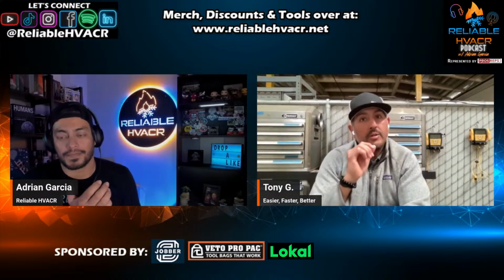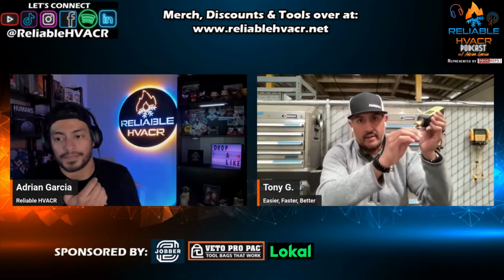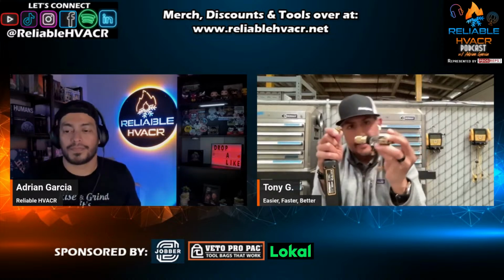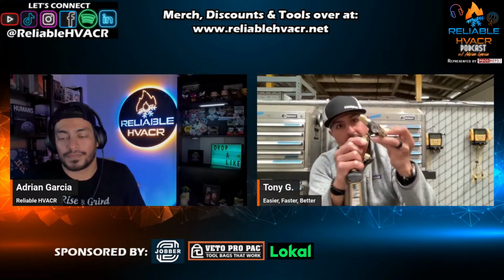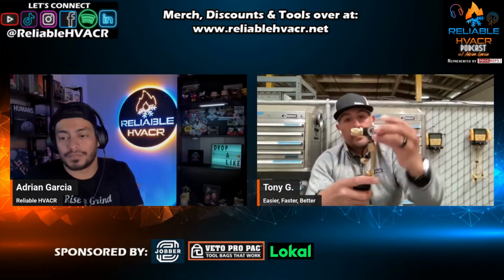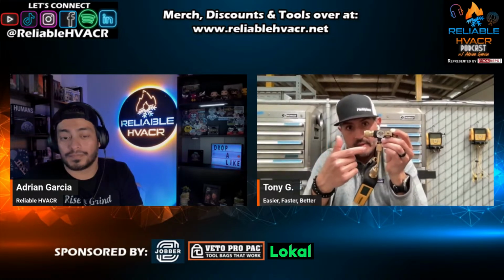But if you want to have the most accurate micron readings, you're going to use a dedicated micron gauge and connect it directly at the system. And so that's what a VCRT allows you to do, is you have this connected on your service port, and you can connect your micron gauge to the side port of your valve core removal tool, and you can measure your microns there. Now, there is one issue with doing it this way, okay?